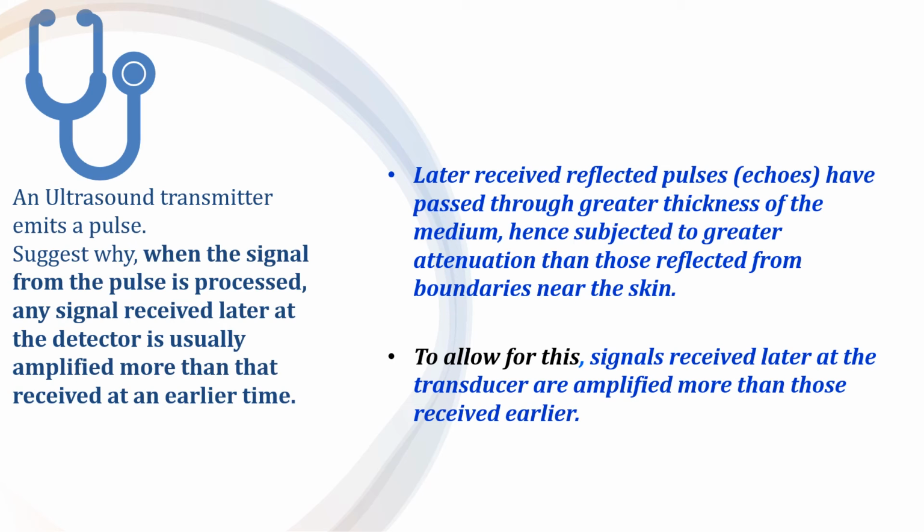Later received reflected pulses have passed through greater thickness of the medium, hence subjected to greater attenuation than those reflected from boundaries near the skin. To allow for this, signals received later at the transducer are amplified more than those received earlier.